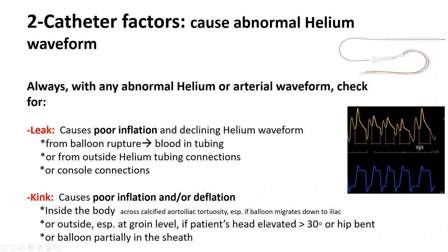Probably the most common kink I've seen is outside the body at the groin level. If you make somebody with a balloon pump sit up, the balloon kinks at the groin level. That's why we should always keep the patient with a transfemoral balloon pump flat at all times. Another reason for kink is the balloon is still in the sheath. So it's not just in the iliac, it's even in the sheath. It kinks because it's not able to expand in the sheath. And this is something you can tell sometimes just by looking at the balloon catheter and seeing that one of the markers is actually outside the body, and by x-rays. So always think of those two, leaks and kink. Leak causes poor inflation. Kink can cause poor inflation and or poor deflation.